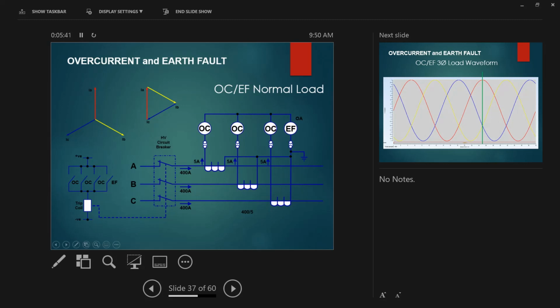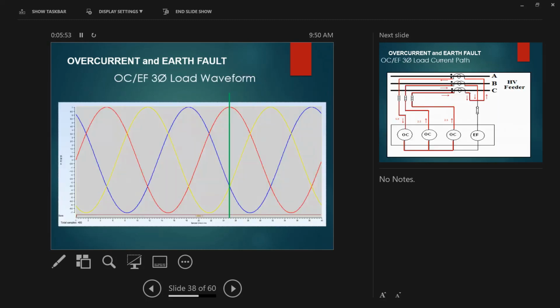Just to give you some kind of idea. Sometimes when you test the relay, you have to rationalize the flow of current in your mind, for you to understand what is happening inside the relay. So you have balanced current ABC, you see the waveform. One cycle here, one cycle, so you end up somewhere here, where one cycle is 0 to 20 milliseconds. So that is one cycle, okay? Once you maintain those distances between these three magnitudes, 120 electrical degrees, you will have a balanced system.